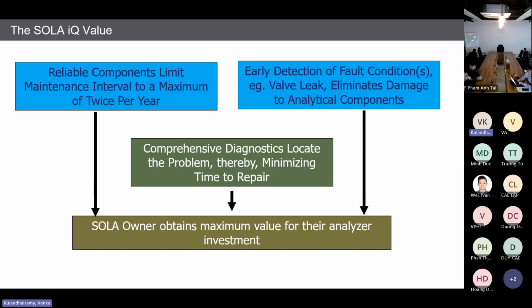But I can say one point from here: all our competitors do not have the PUVF technology. They have a UV technology, but they do not have a Pulsed UV Fluorescence technology, because it is patented by Thermo. So Thermo only has the technology. That's why our Thermo SOLA IQ can measure low concentrations very accurately. If a customer wants to measure PPB level, it can be done. Also, it's very steady, very stable. From PPB level up to percentage level, we can measure with our SOLA IQ analyzer.